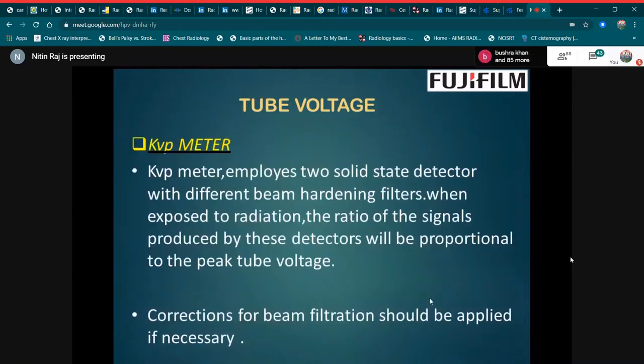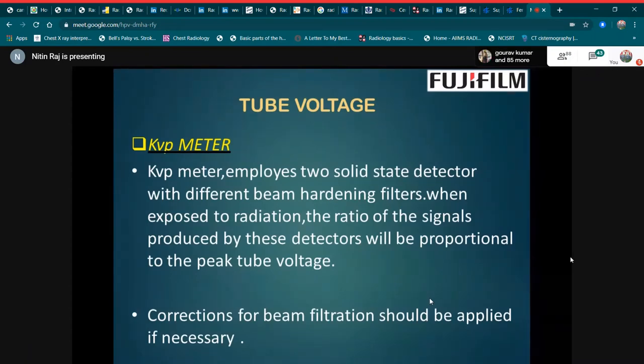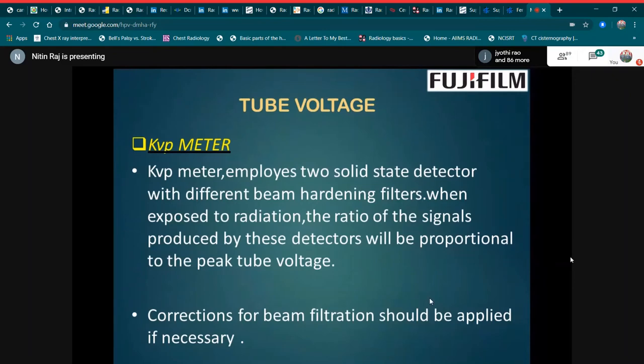Next is tube voltage measurement. The kVp meter is the tool used for tube voltage. The kVp meter employs two solid-state detectors with different beam-hardening filters. When exposed to radiation, the ratio of the signals produced by these detectors is proportional to the peak tube voltage. Correction for beam filtration should be applied if necessary.